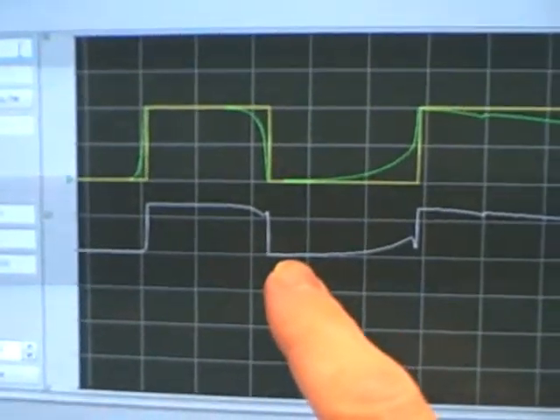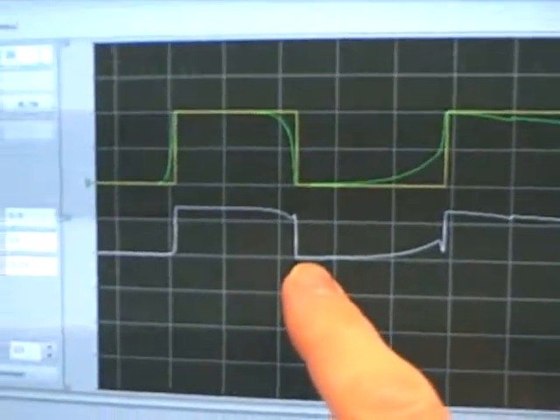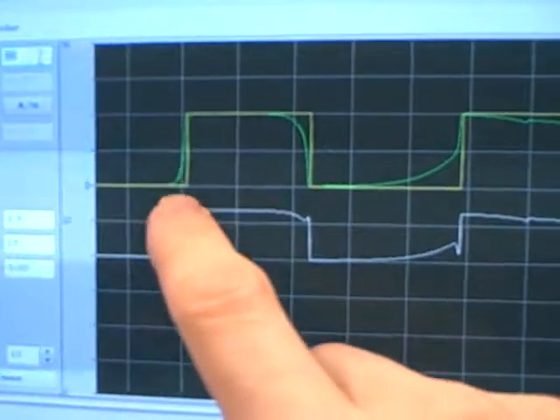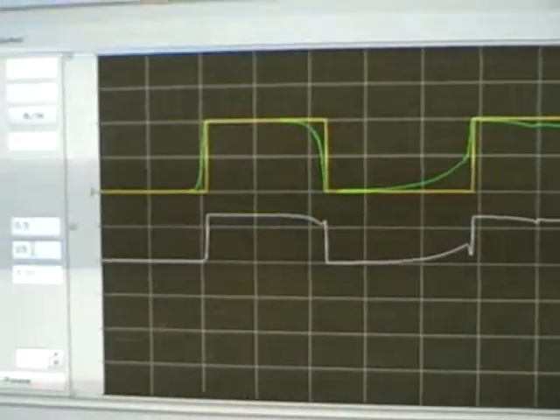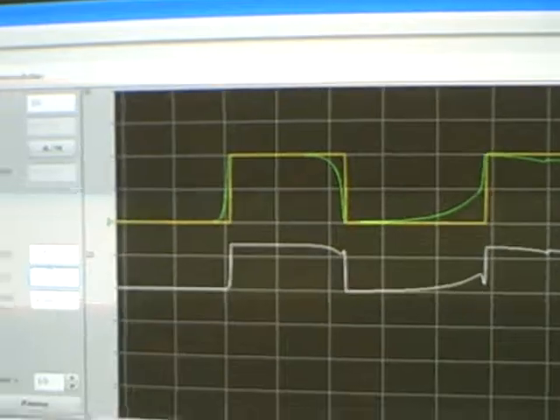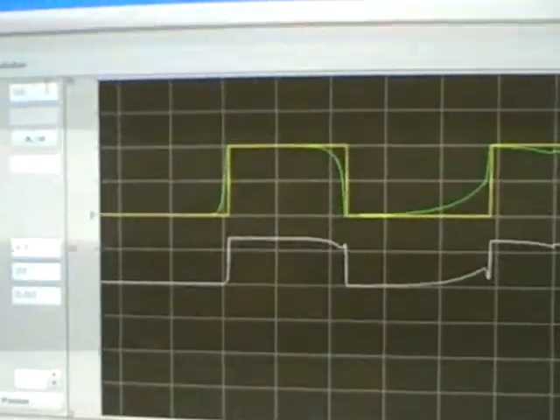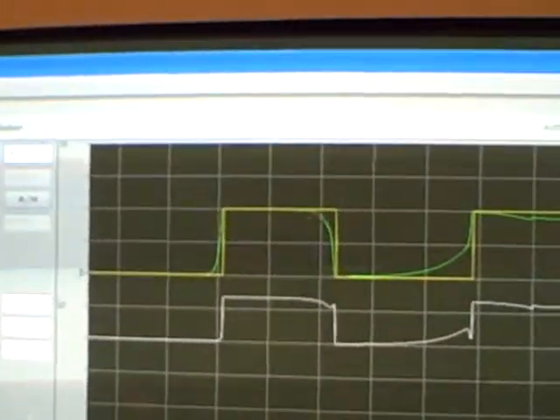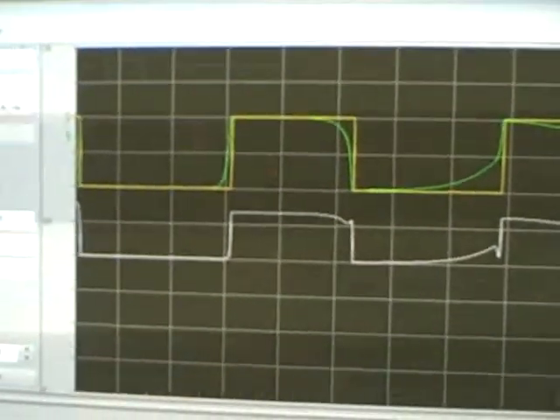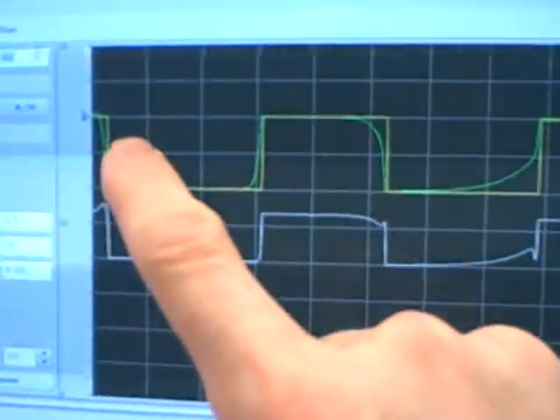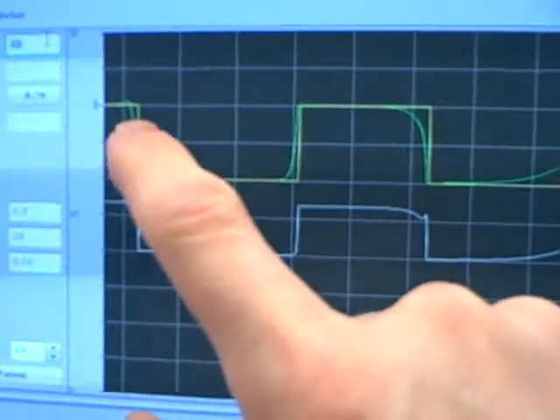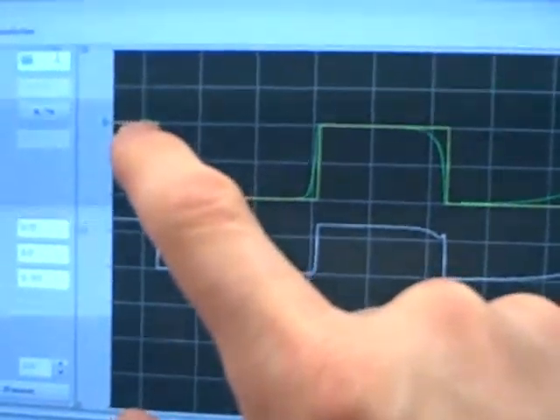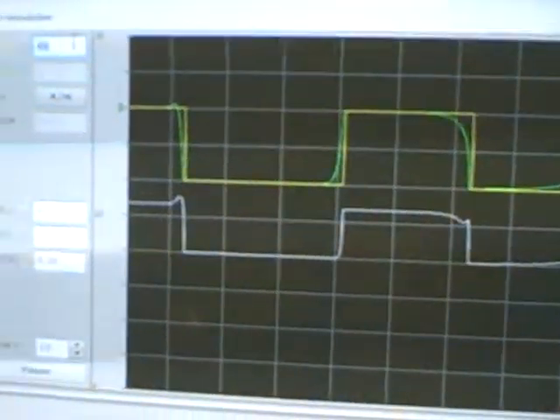You can see how well this fast-acting, self-regulating process responds to integral control action from the controller. But we're still not overshooting, no oscillation, so I think we can go even more aggressive on the integral. So I'm going to go 20 repeats per minute. I'll jump the set point back up to 40% to watch the response. There we go. Set point jumps up to 40%. Process variable very rapidly rises up. Little bit of overshoot, and then settles at set point.